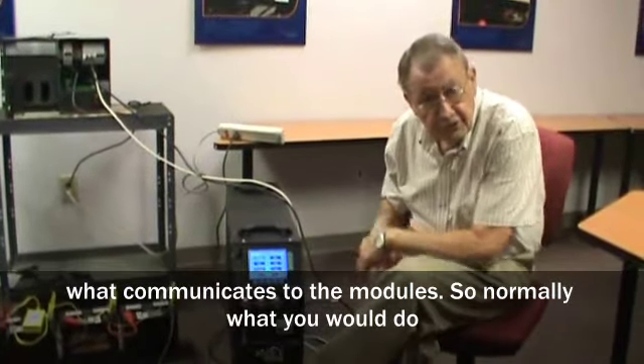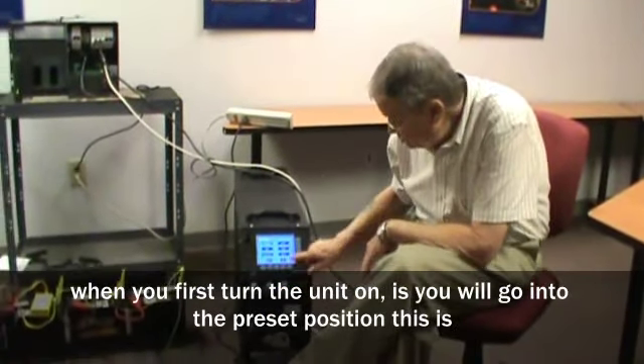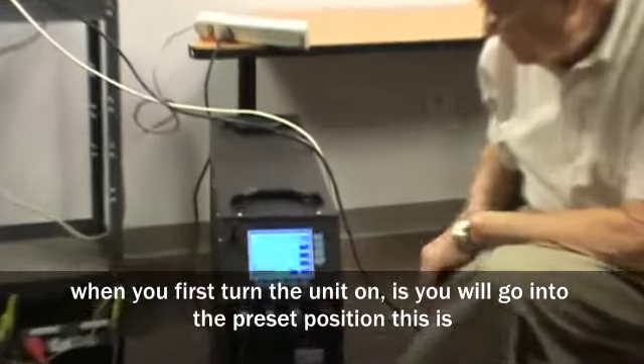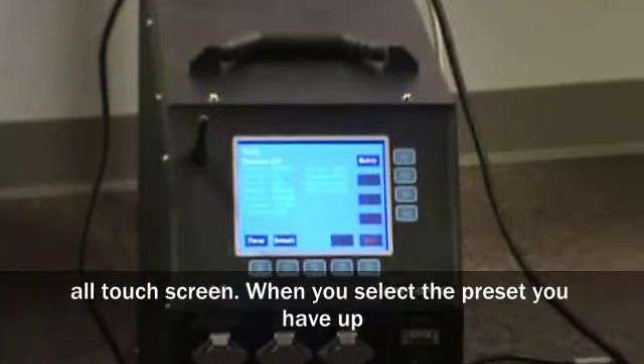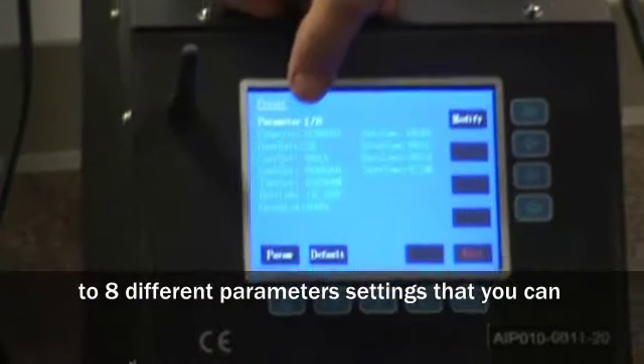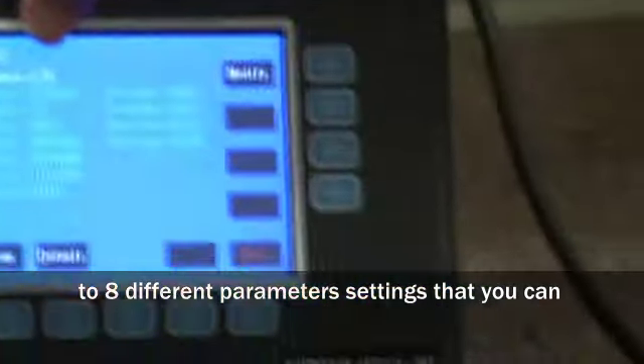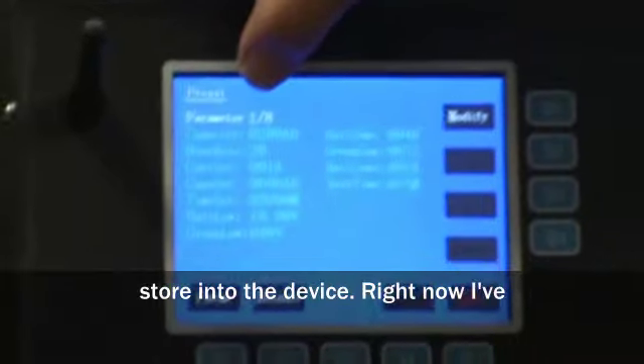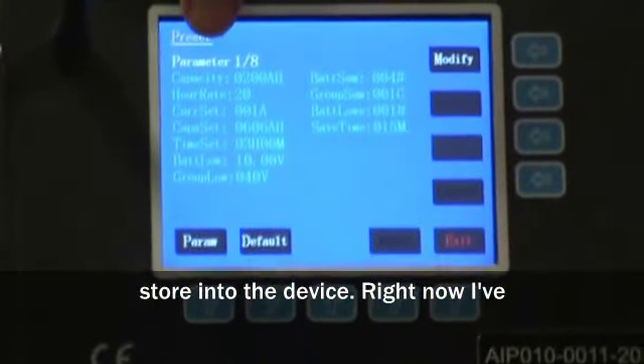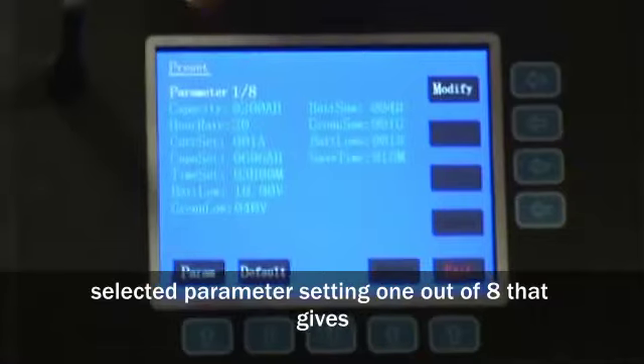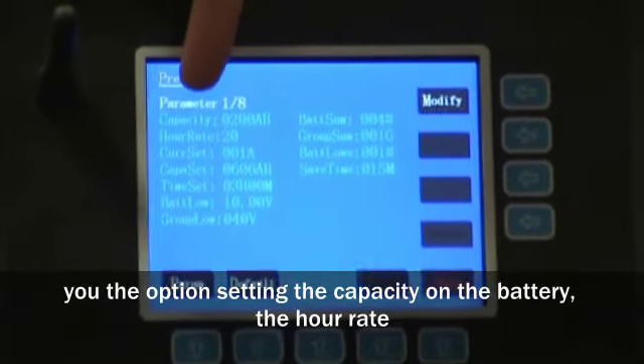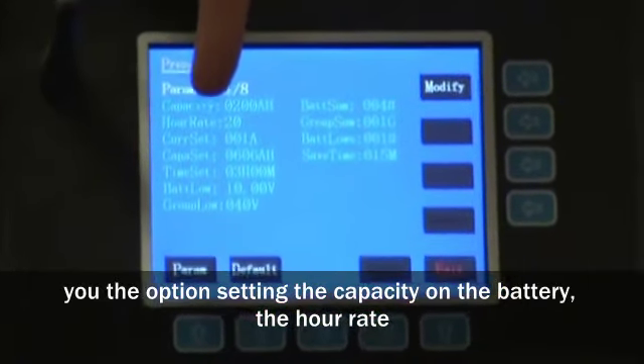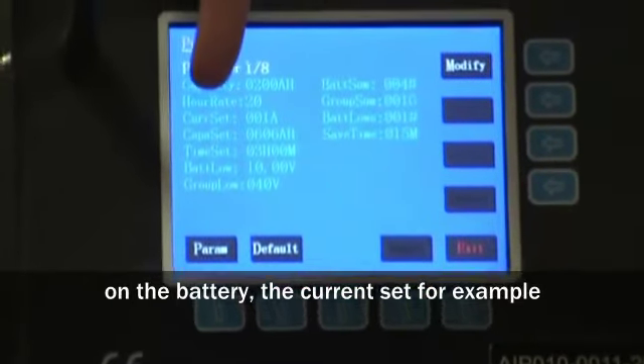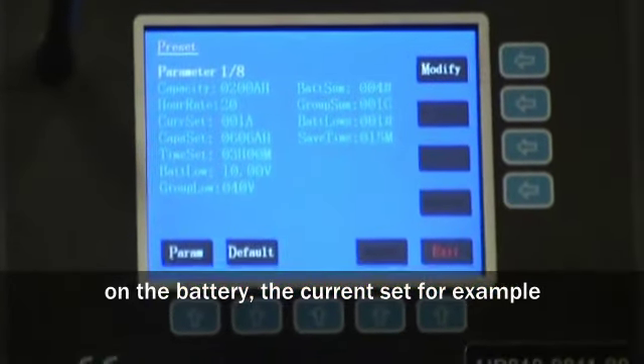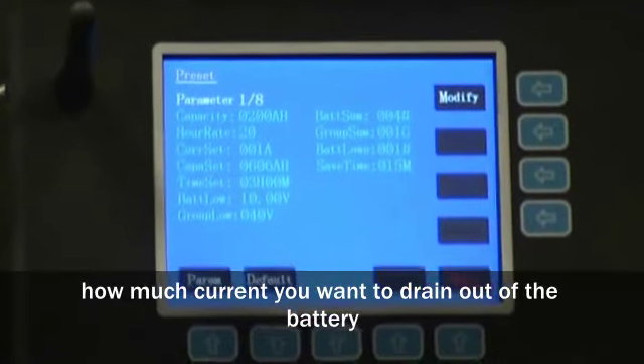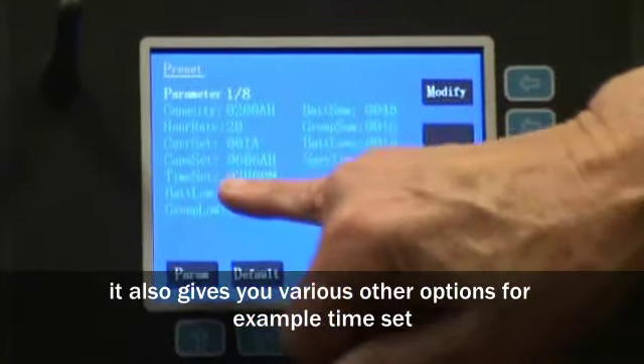So normally what you would do when you first turn the unit on is you would go into the preset position. This is all touch screen. So you select the preset, and you've got up to 8 different parameter settings that you can store into the device. Right now I've selected parameter setting 1 out of 8. That gives you the option of setting the capacity on the battery, the hour rates on the battery, the current set, for example, how much current you want to drain out of the batteries. It also gives you various other options.